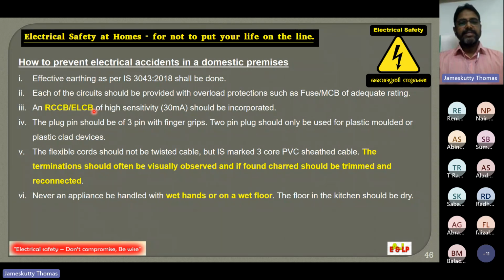Now, actually, what is an RCCB? It checks the difference between the incoming current and outgoing current. I explained to you, consider the winding of our motor, our water pump. Suppose it is shorted. What will happen? The phase and neutral will come in contact, and it will create a high current. High current means not a small leakage current in the milliampere range. Say it can be 5 ampere or 10 ampere. It can cause damage to our house. Immediately, our protection should work.